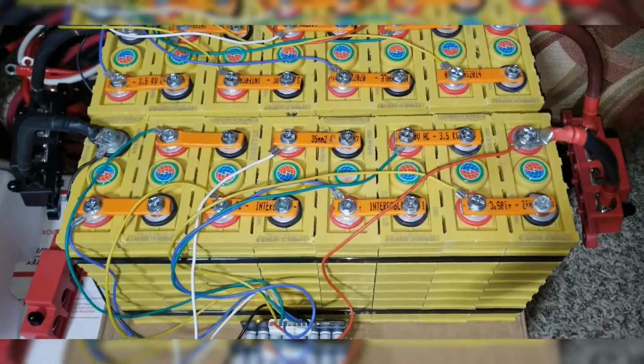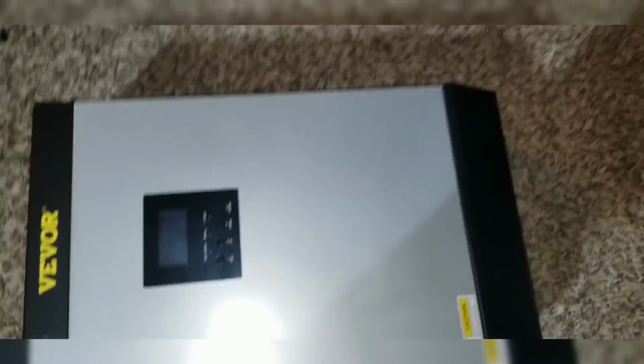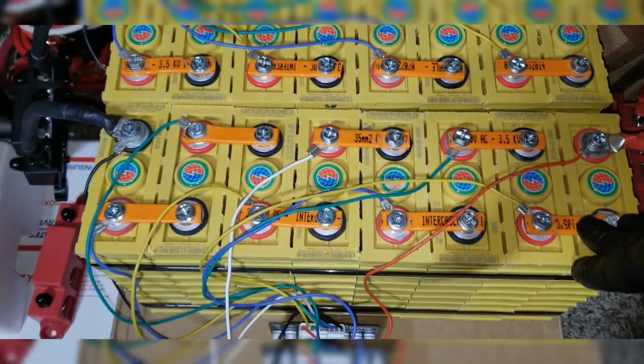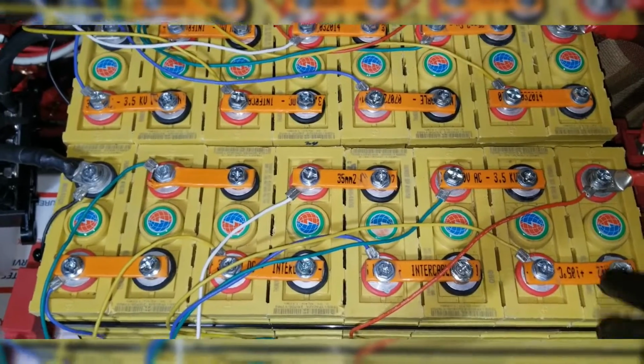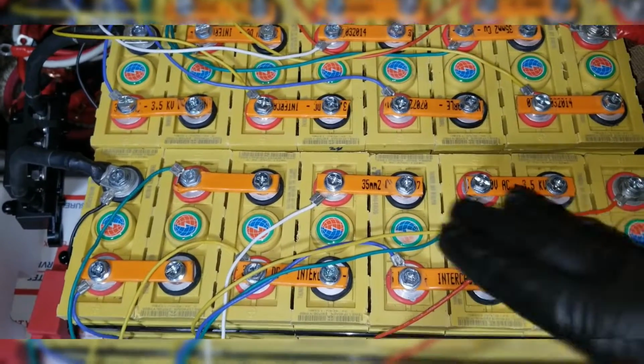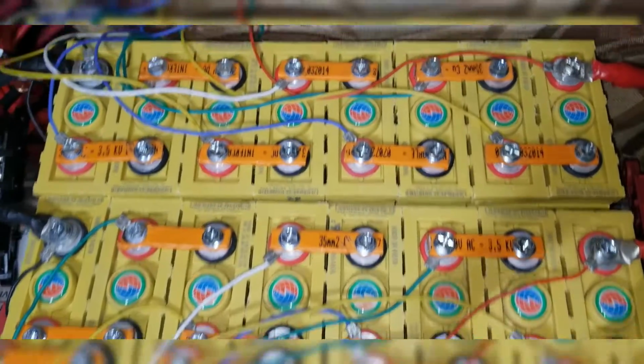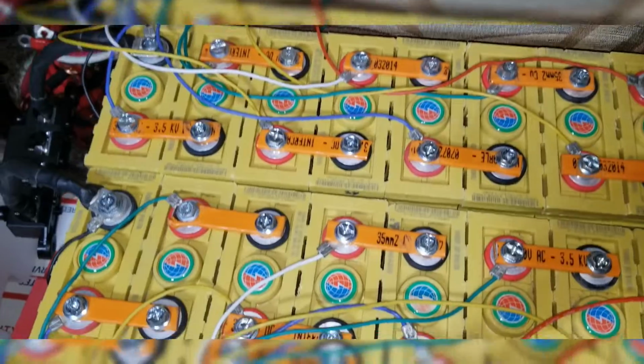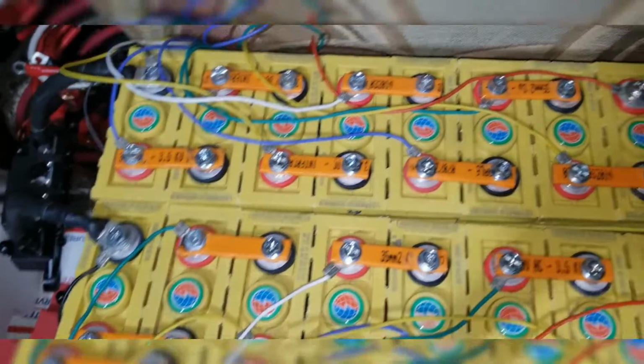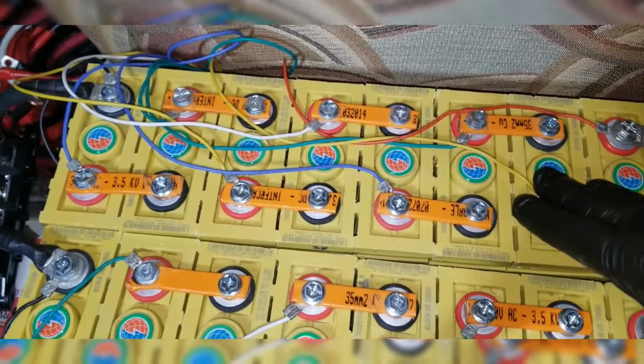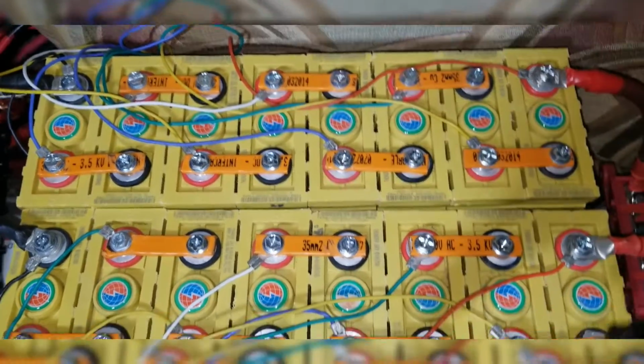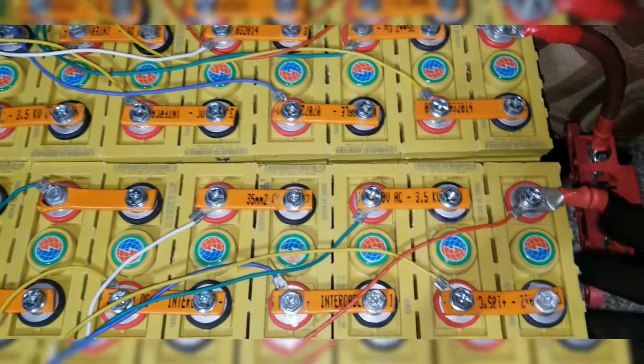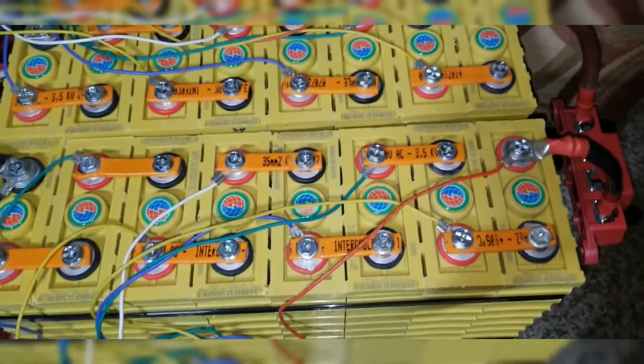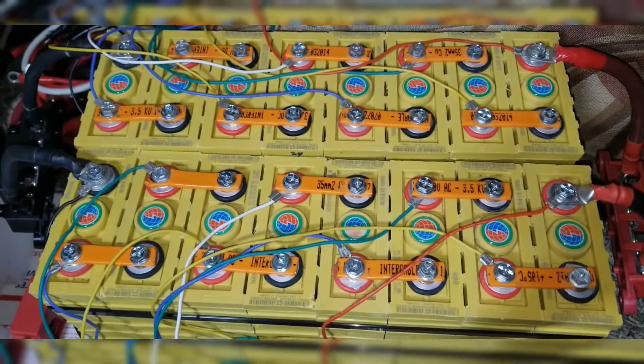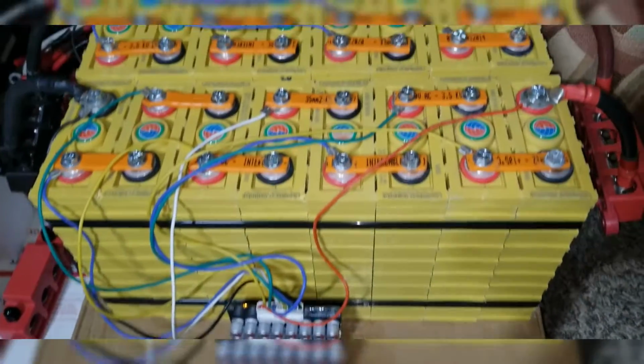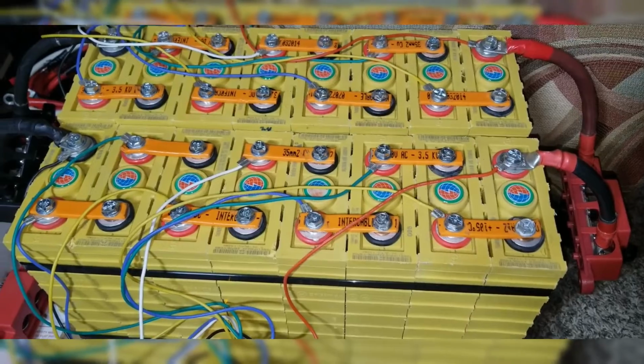So we'll see how this works in conjunction. It's 40 amps here on 24 volts, because each cell is 40 amp wired in series - the voltage goes up, the amperage stays the same. So 40 here, 40 there, at 24 volts. If I wired it for 80 amps at 24 volts the way I set them up, but going to 48 volts instead, the voltage goes up and the amperage stays the same, so we only have about a 40 amp battery bank - small but powerful, just for a test to see how everything works.